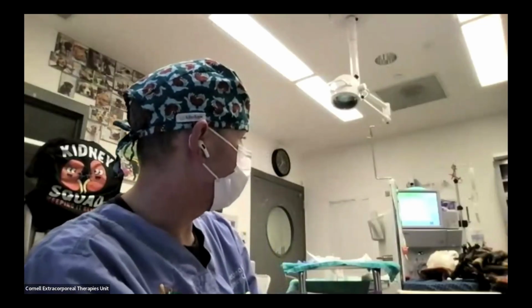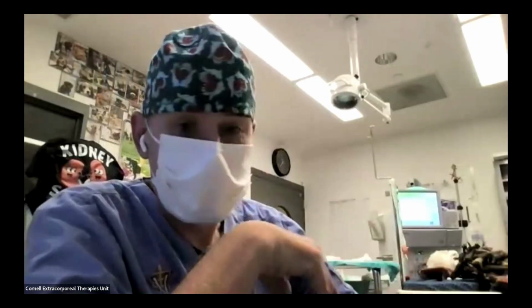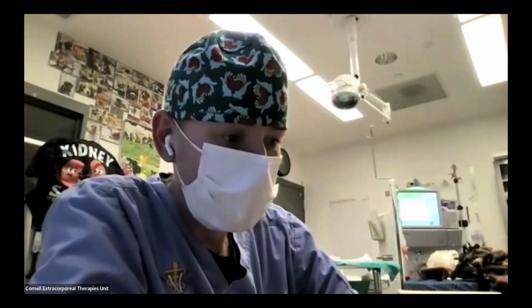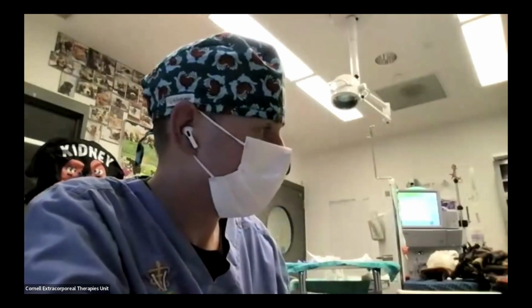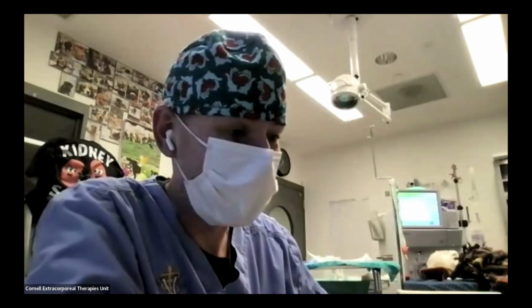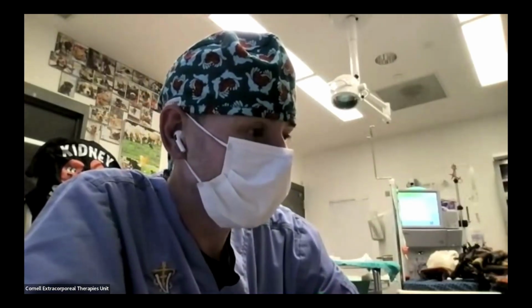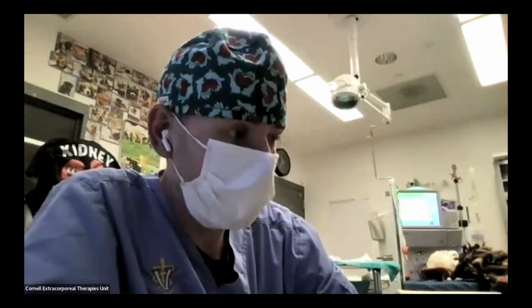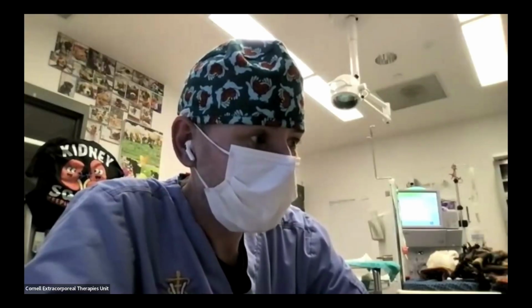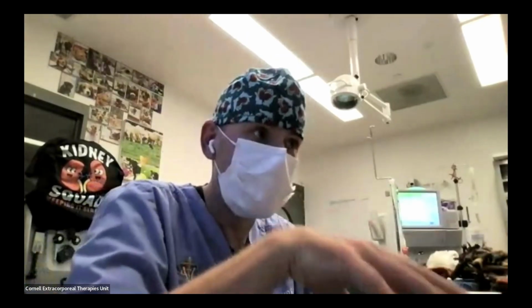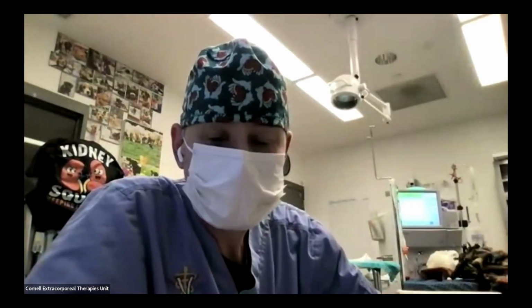But after we get off here, I may try and hook up that access pressure line. Like I said, if I got things going a little sooner and setup had happened a little more smoothly, I was going to try and set up today to have that going as well. The jerry-rigged one. But the last couple of treatments in this one, I watch her access line like a hawk for any type of little air bubble starting. The pump doesn't struggle, the pump just keeps turning, but you can kind of tell by the movement of the line when it's sucking up against the cava inside. So those have been things that I've used as surrogates for that access pressure, I guess. Thanks. That makes sense.